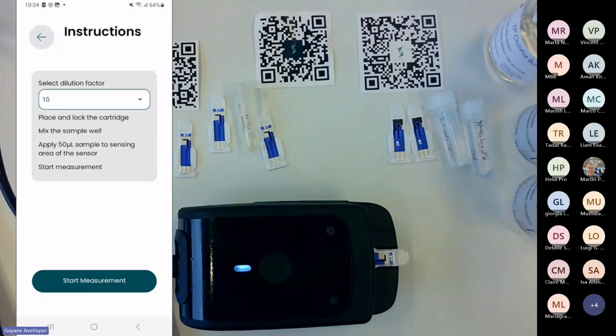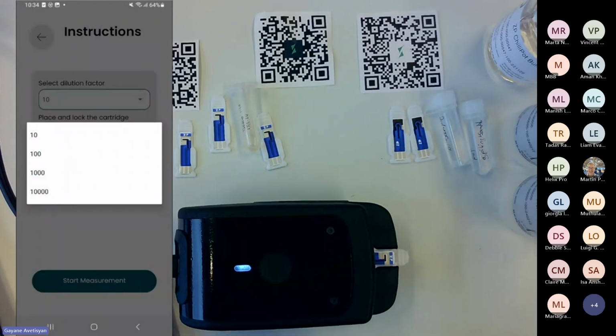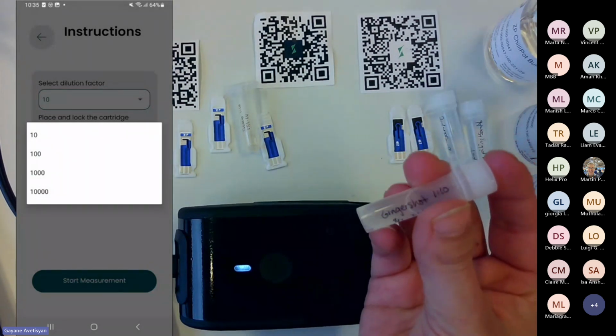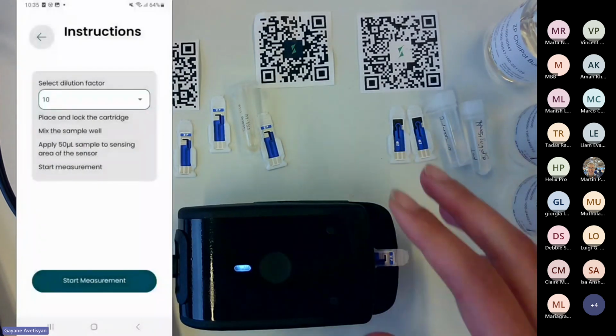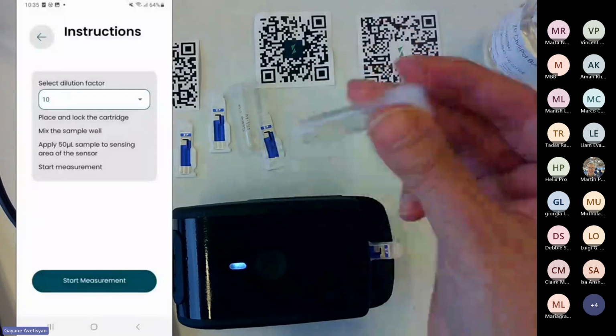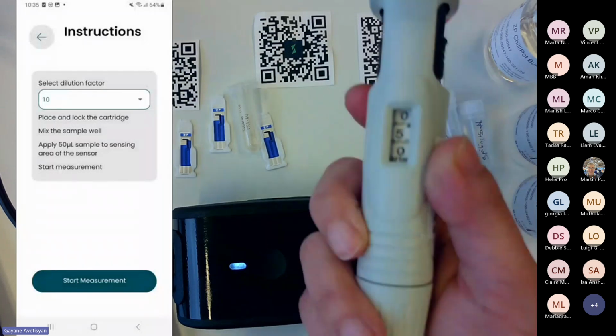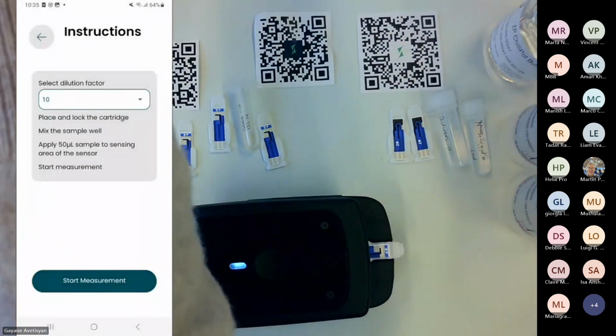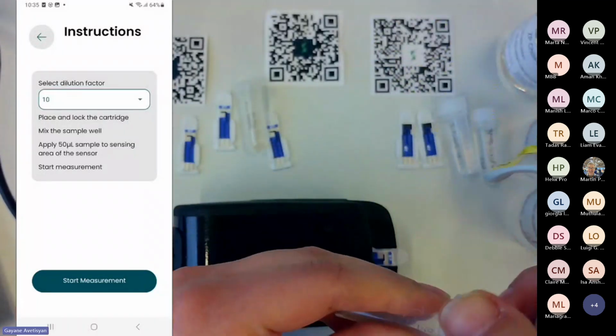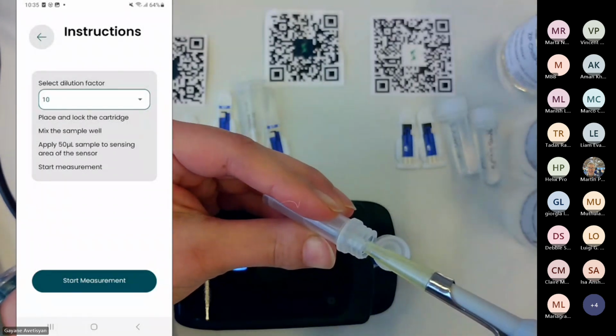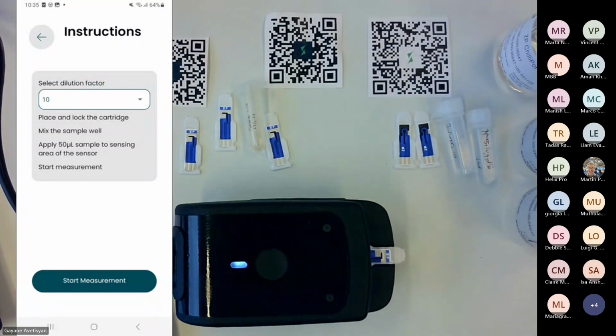And as we see, the first thing on the instruction screen asks us to choose the dilution factor. And when I click on it, I can see that I have 4 different options, 10, 100, 1,000, and 10,000. At this point, we will need to choose 10 because the solution that I already prepared is a 1:10 ratio. This is done. Now it asks me to place and lock the cartridge, which I already did, and mix the sample well. And after that, I will need to pipette 50 microliters of the solution. Try to put it here, you can see. Now I will try to cover all the electrodes, and I'll be careful to not scratch them. Yeah, it's done. Once it's done, I can press start the measurement.